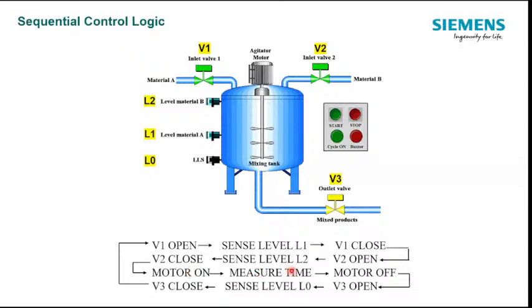After the time period of half an hour, the motor will turn off and V3 will open. Once the material has been drained and reaches the lowest level L0, that will be sensed to close V3 and open V1. So now my process has started running continuously and automatically unless I press the stop push button.